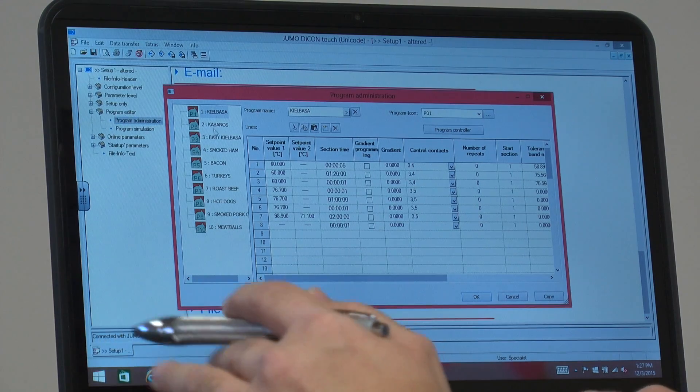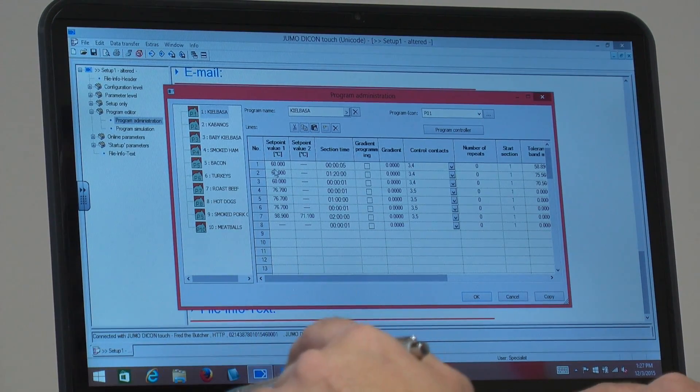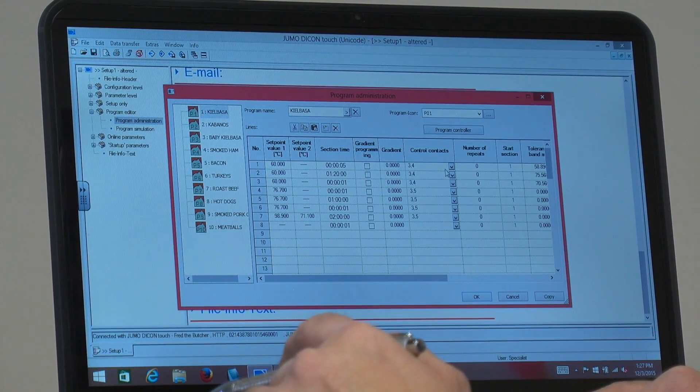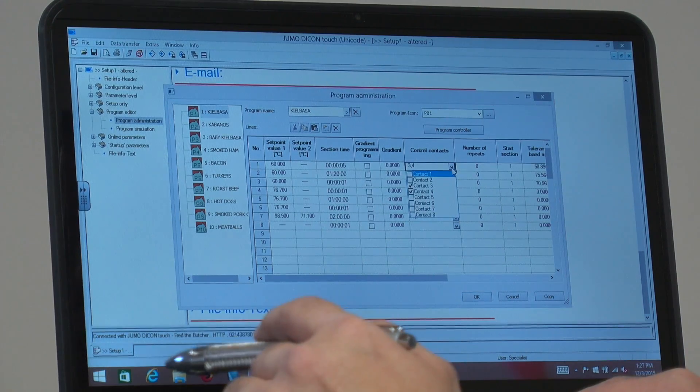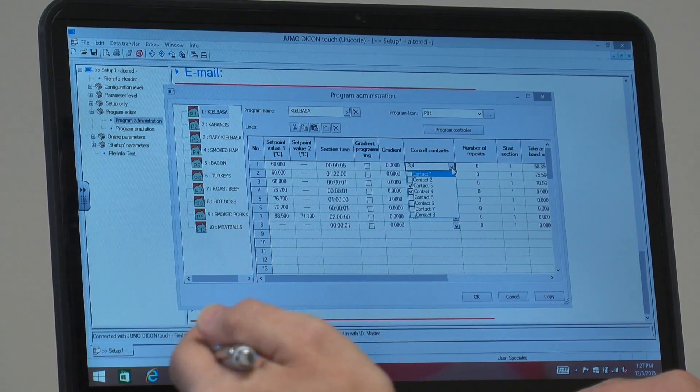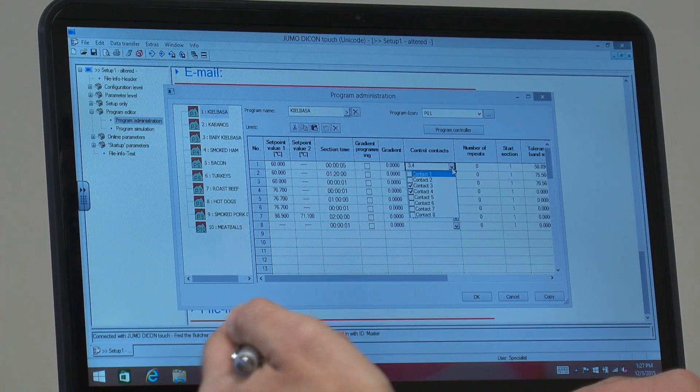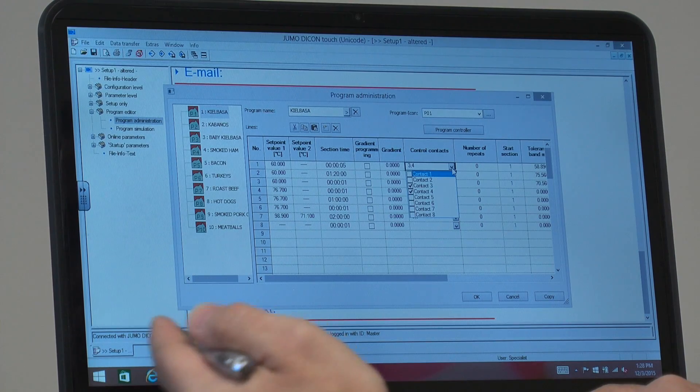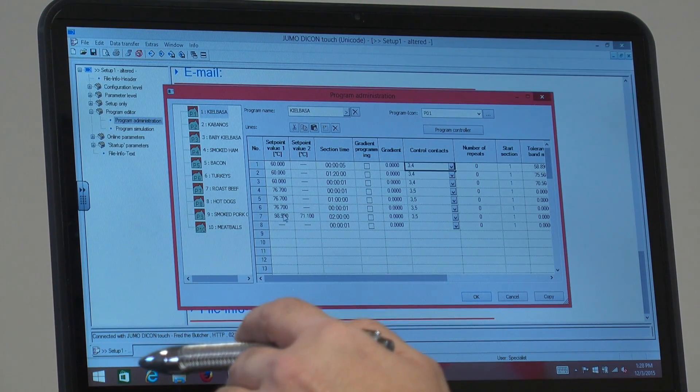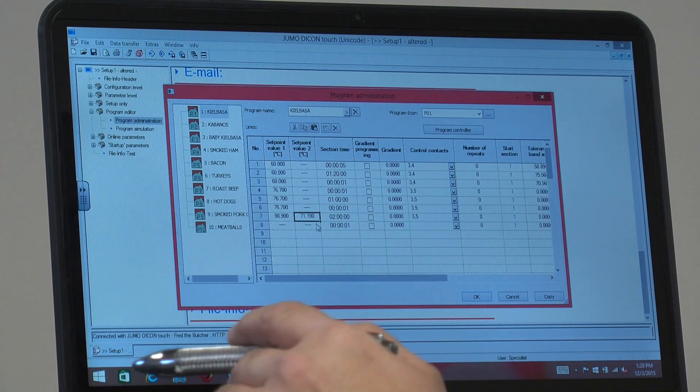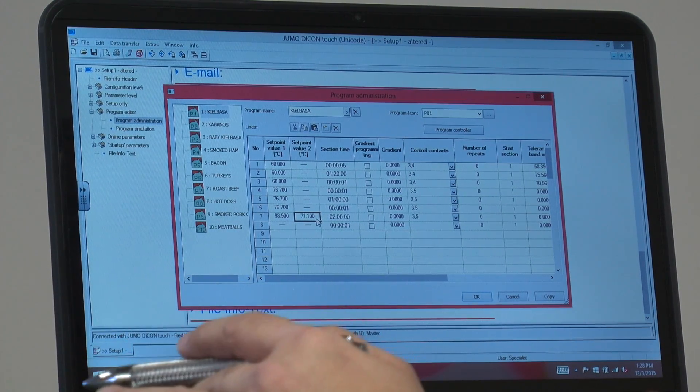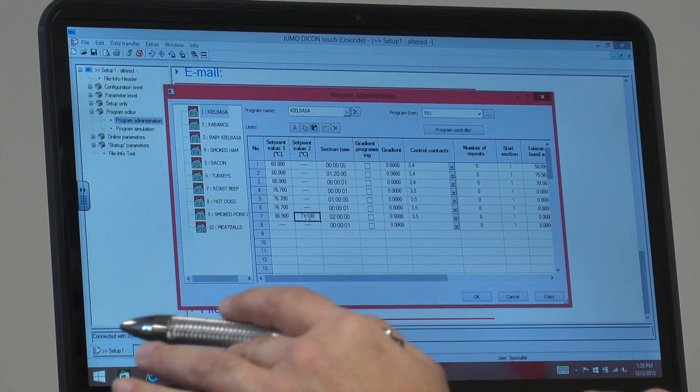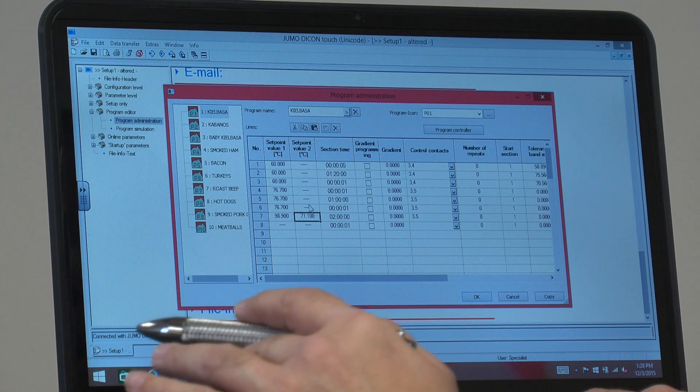The key one here is the program administration. There's ten programs, different types of meats that they have. There's different temperatures. There's different relays that are going to be triggered for, in their case, smoke. There's a damper. There's steam that's used for generating humidity. Those options are going to be turned on and off and then here at the end in this particular case when it reaches 71.1 degrees Celsius the program will be ending.